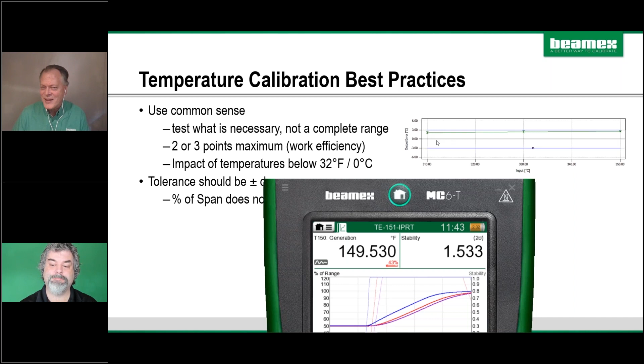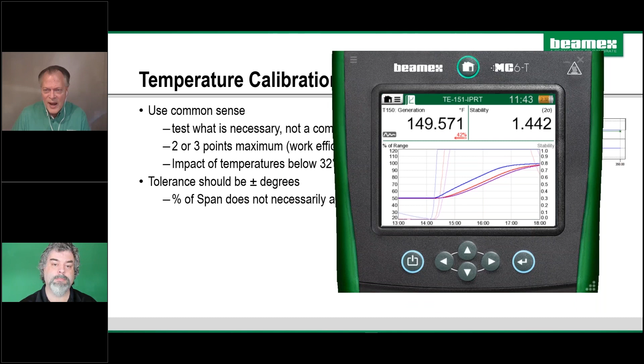Because let's see if I move this down. So here's this example. If we did this test 310 to 350 and then came back down, guess where it would land? It would land here, and it would land here. It's very repeatable. So in our example right now that's running, we've got to give it some time to stabilize here, but we're going to have a straight line across the tolerance line. And if we went back down and we waited for that nice stability factor, where it's going to land right on top of it.